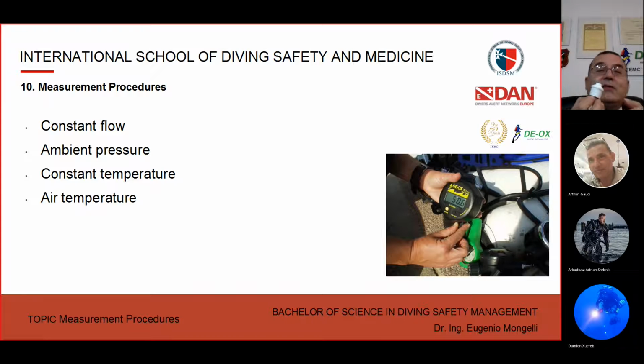Then when you have done the calibration, even if you leave the sensor in high humidity, you don't care. Okay, maybe the concentration of oxygen will drop when you leave it in air, of course, because of the high humidity. But when you go and analyze the cylinder, the gas is perfect. So that's my first tip: always use a cylinder with air for making the calibration. Unless you are like now in my office in Milan, where you have 21% and 50, 60% humidity, a perfect environment, and then you may use ambient air for the calibration. Okay, understand? But that is extremely, extremely, extremely important, not only for the oxygen, but also for the other gases.